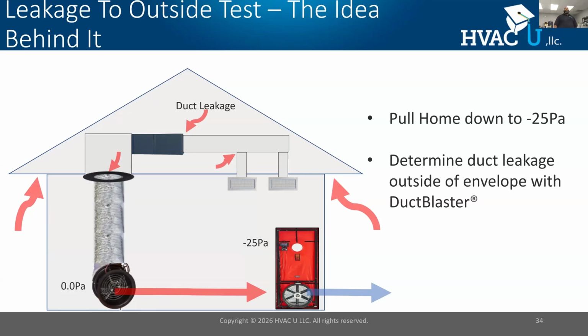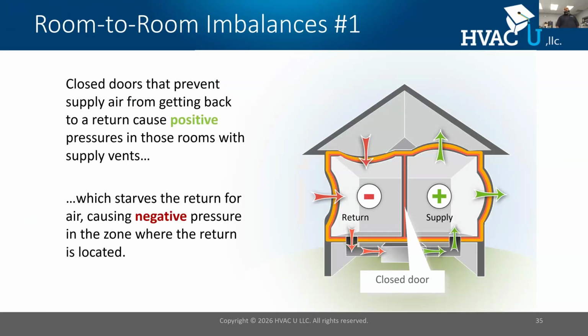Absolutely. Great call out. All right, so our next procedure is going to be room to room imbalances. What is that? This is another procedure that we're going to use. The way this procedure works, I have to have the air handler running, or the blower on the furnace running. And when I'm running that blower on the furnace, what I'm looking for is, do I have enough CFM going into the room? And do I have enough CFM going back to the air handler?